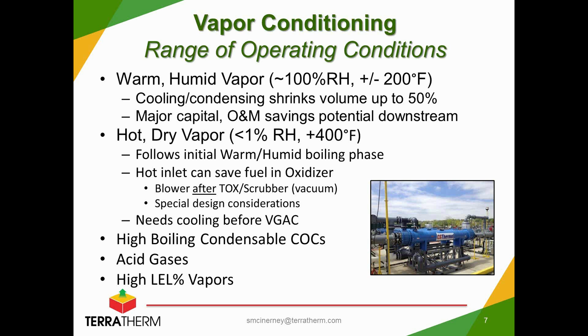When you do that, oftentimes you're looking at some unique equipment configurations where the high temperature vapors, upwards of about 400 degrees Fahrenheit, really aren't suitable to be passing through a blower that would then push the vapors through the oxidizer. Oftentimes you're talking about an induced draft configuration with the blower after the oxidizer scrubber. And there are other special design considerations around that kind of configuration, where the entire system is under negative pressure or vacuum. But when you're not looking at an oxidizer, most definitely you need to be looking at cooling before you get into an activated carbon system.